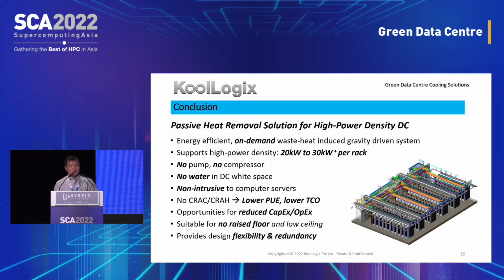In conclusion, it's a passive heat removal solution, meaning it does not require any pump or compressor. It's designed for high power density data centers, 20 kilowatts and above depending on the situation. Through measurements, it can actually dissipate up to 34 kilowatts, depending on surrounding conditions, but typically we design for about 20 kilowatts. So: high power density, no pump, no compressor, no water in the white space, non-intrusive to the data center itself, resulting in lower PUE and lower total cost of ownership.